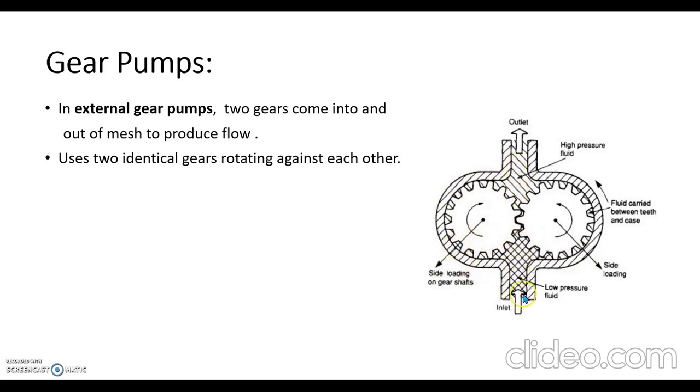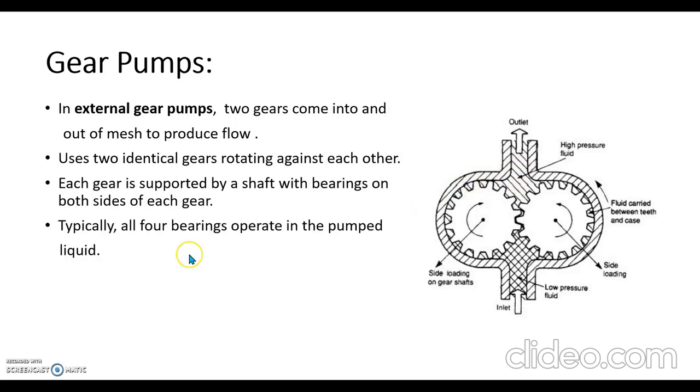This is inlet and this is outlet. Inlet flow will be of low pressure. It is pressurized as it passes through the small clearance between the teeth and housing. This is also the pathway of the fluid. Each gear is supported by a shaft with bearings on both sides of each gear. There will be a total of four bearings and it can withstand high pressure, so it is used in high pressure applications.